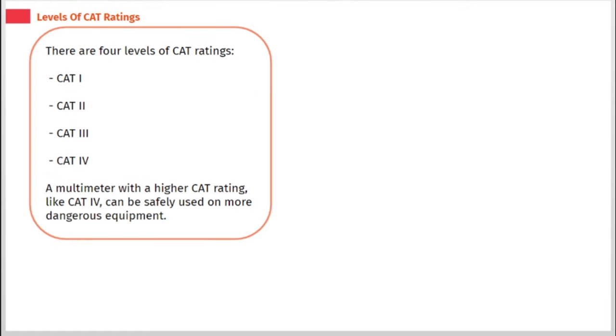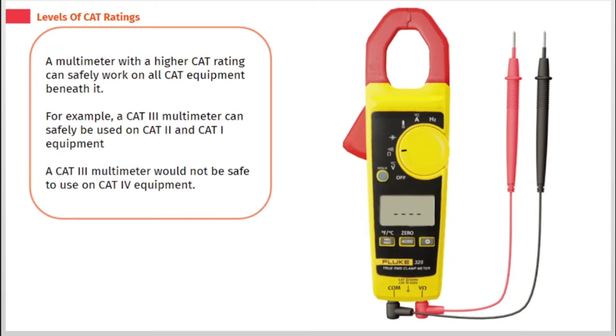There are 4 levels of CAT ratings: CAT 1, CAT 2, CAT 3, and CAT 4. A multimeter with a higher CAT rating, like CAT 4, can be safely used on more dangerous equipment. A multimeter with a higher CAT rating can safely work on all CAT equipment beneath it. For example, a CAT 3 multimeter can safely be used on CAT 2 and CAT 1 equipment. A CAT 3 multimeter would not be safe to use on CAT 4 equipment.